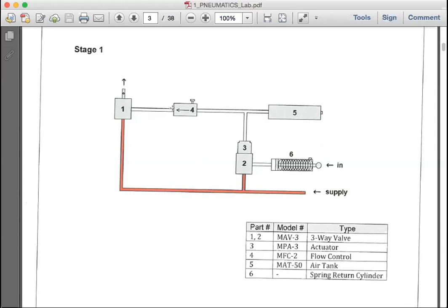Okay. Also on your flow control, there is an arrow. The arrow indicates the engraved direction of this flow control, in which way the flow is controlled. So if you allow the pressure from left to right, it's not controlled. The controlled pressure is only in the direction of the arrow, so it's from the right to the left. Okay, so here, initial stage, the pressure is here. The next stage would be activation of the stem of number 1.